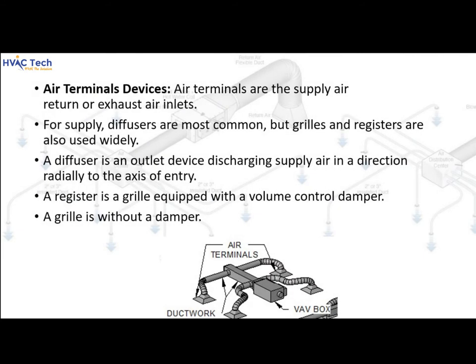Air terminal devices are the supply air outlets and return or exhaust air inlets. For supply, diffusers are most common, but grills and registers are also widely used. A diffuser is an outlet device discharging supply air in a direction radially to the axis of entry. A register is a grill equipped with a volume control damper, while a grill is without a damper.